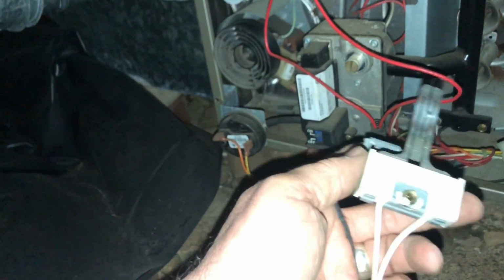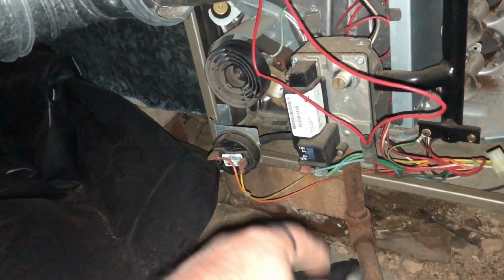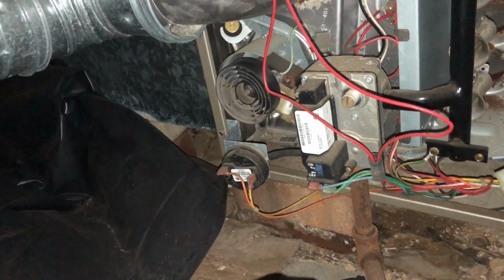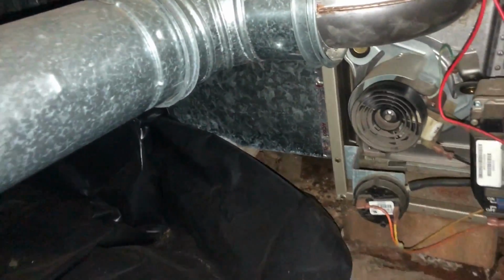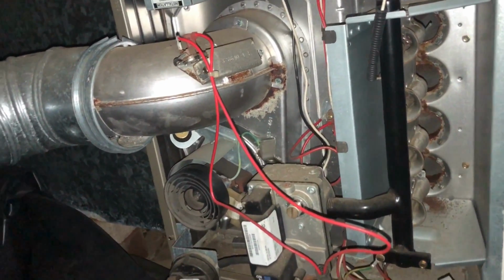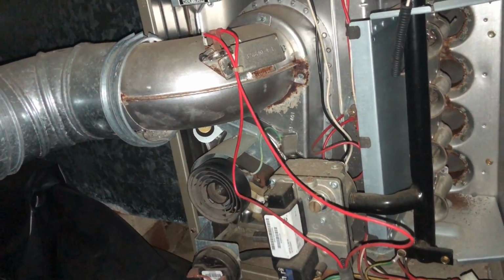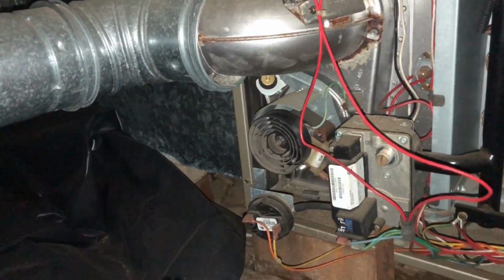They're selling this house and we'll let the home inspectors stir up all the trouble of the flue motor sounds and whatever. It sounds like I'm sure it's rusted all inside and getting very close to the end of its life anyway. The heat exchanger in the furnace may be okay, but that induced draft motor sounds terrible. So let's see what we can do here.